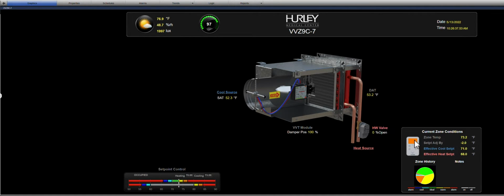We look over here and we see orange, and it looks like the area is not satisfied as much as it is satisfied. So over 50% of the time, it's not in the green space. It's not really in that comfort range. Well, let's take a look. Right now we have a zone temperature of 73.2, which is actually not bad.